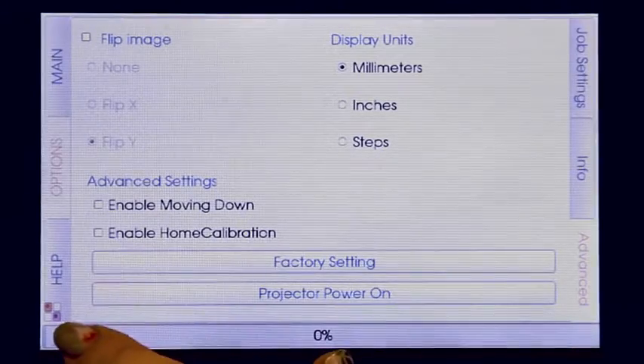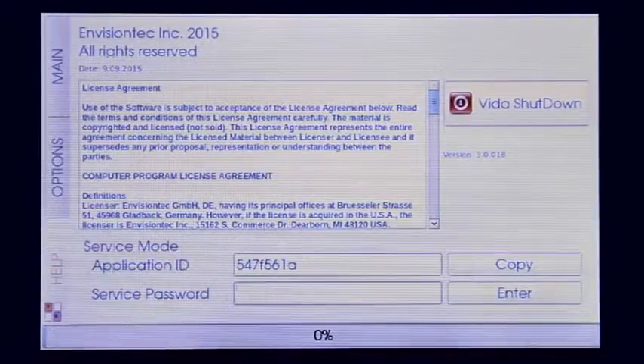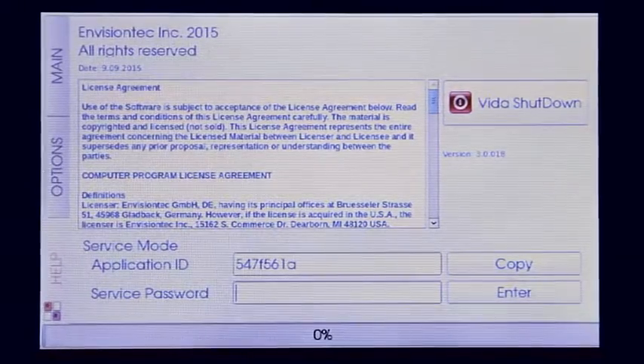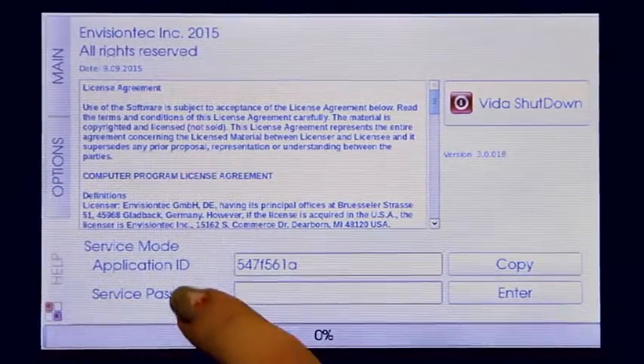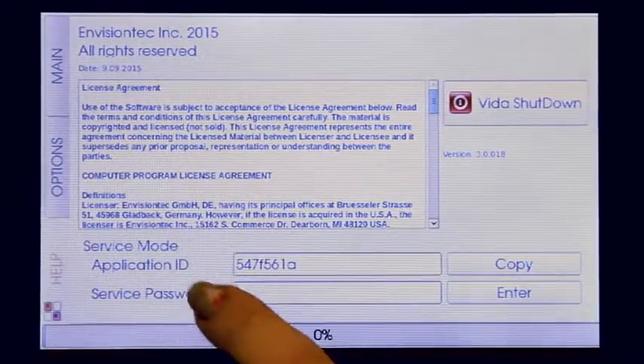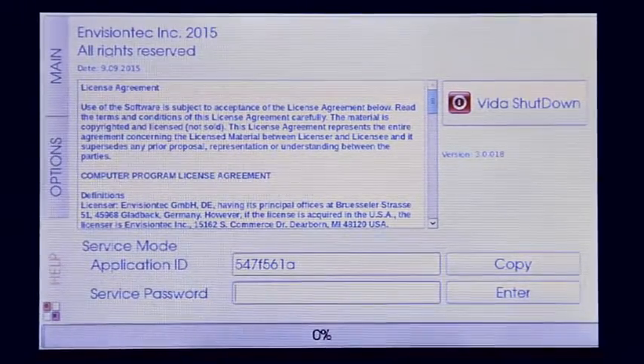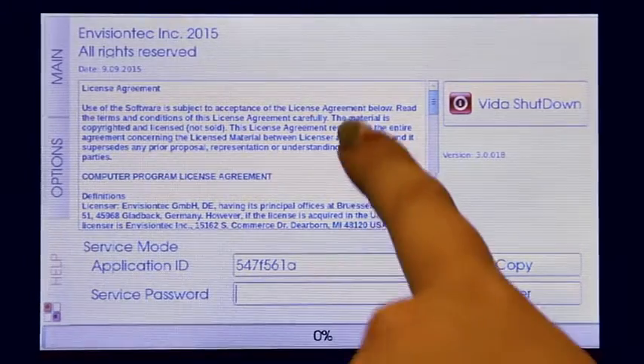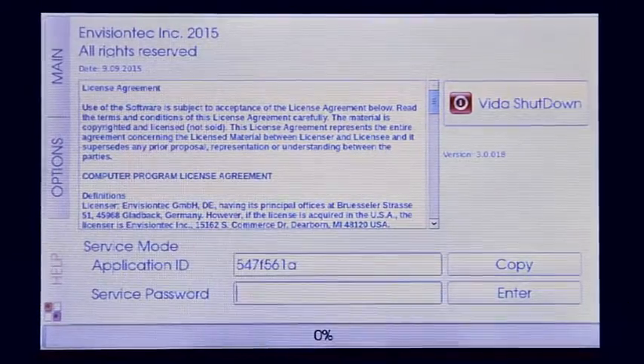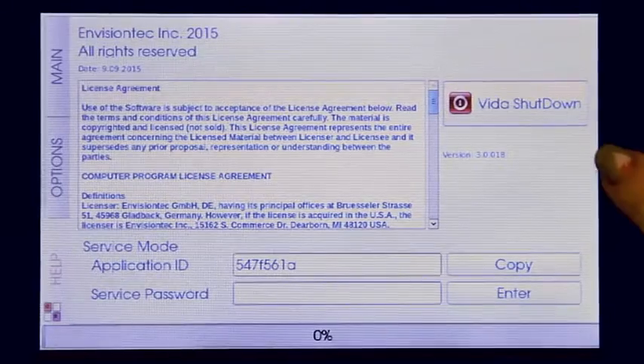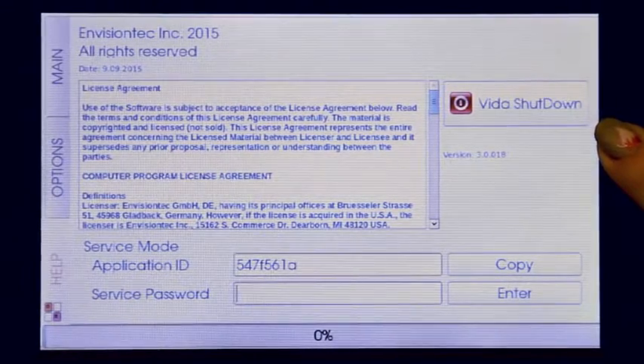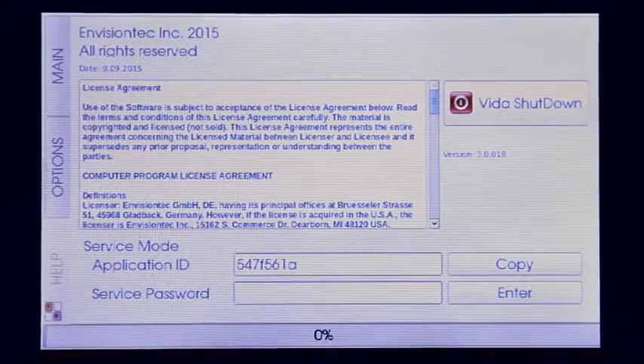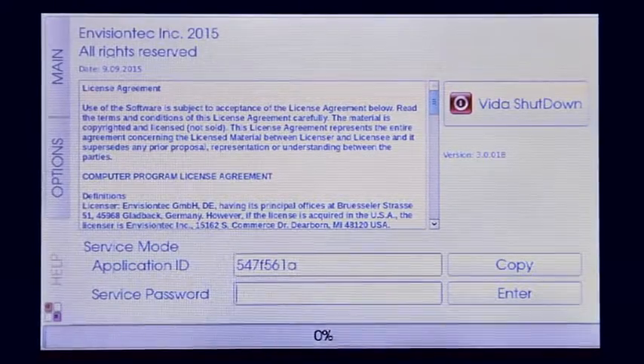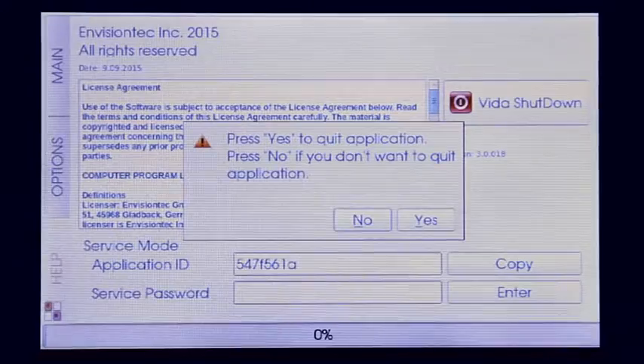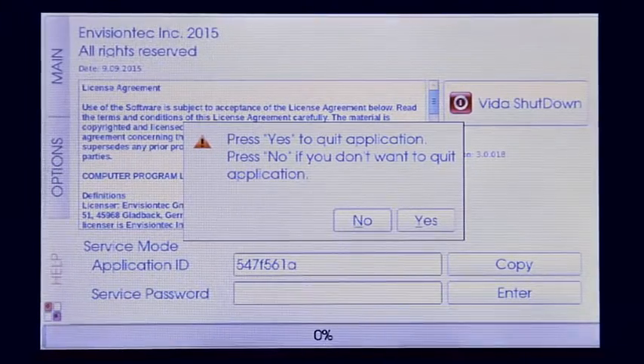If we go back to the left, the very last tab says Help. If I click on that, this will take me to a screen that allows the technicians that are helping you to unlock service mode, should we need to, which allows us access to other features. It shows our licensing agreement for the software. And then right here, you'll notice the Vida shutdown button. When you are done for the day and you wish to shut the Vida down, you come into the Help tab, you select this button. It will ask you if you want to quit the application. You would push yes, and the machine would turn off.